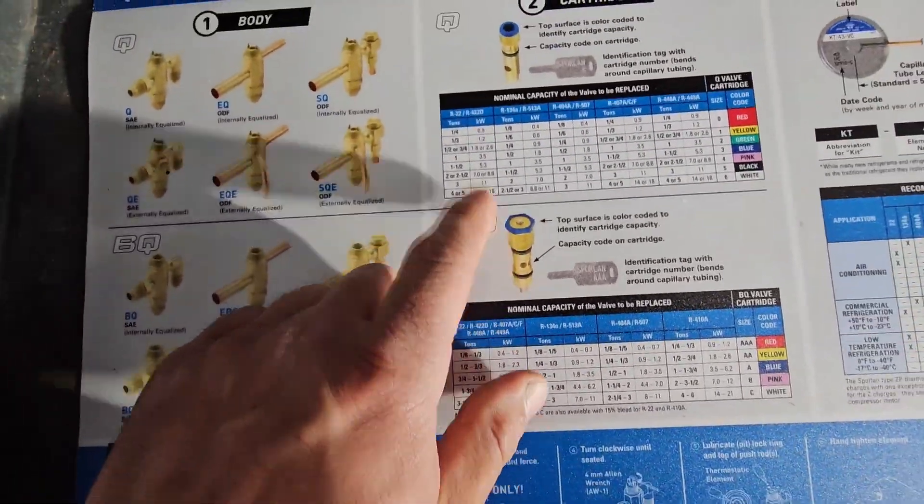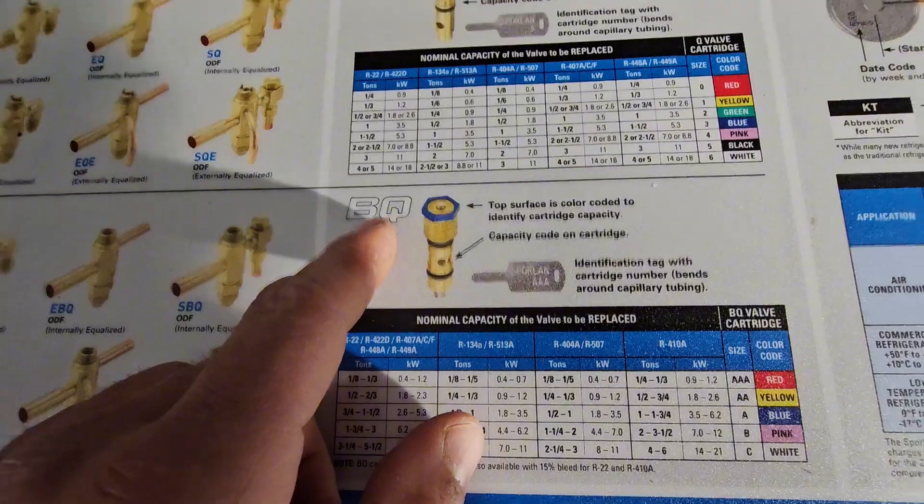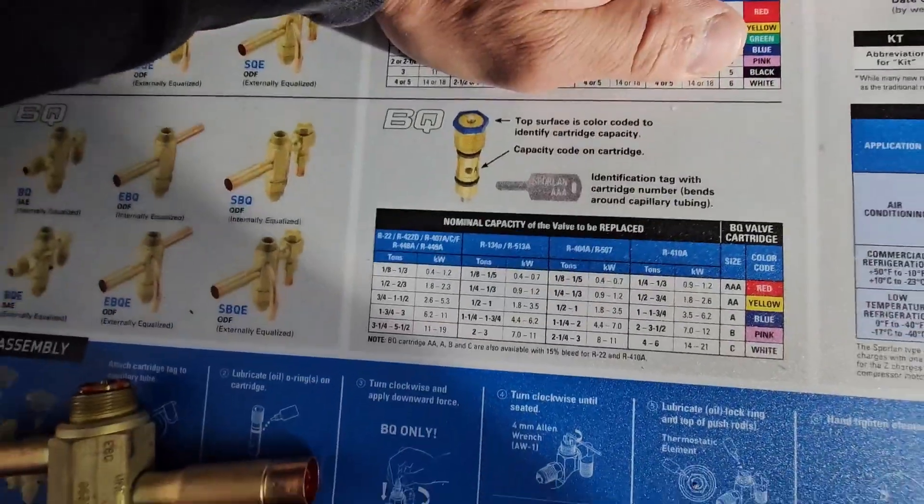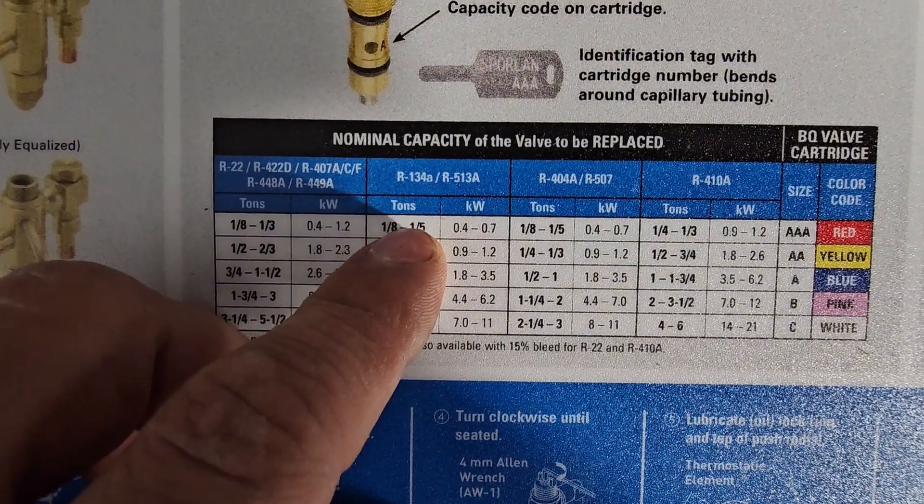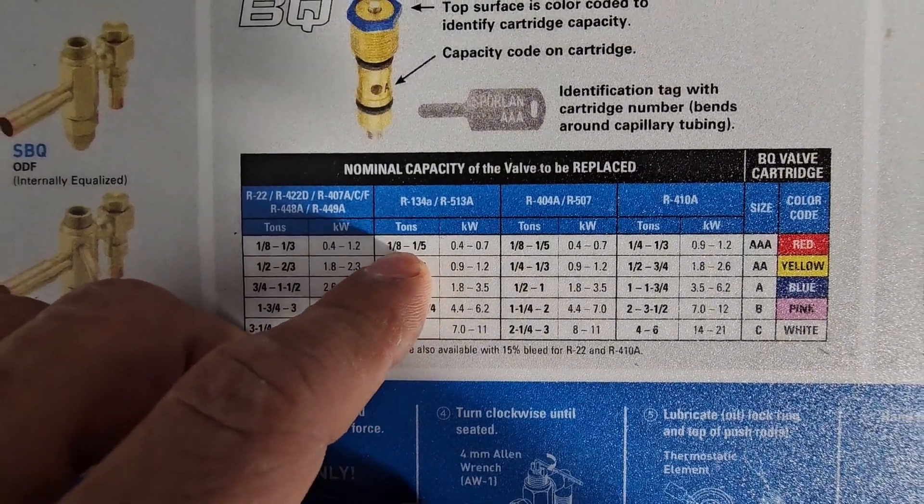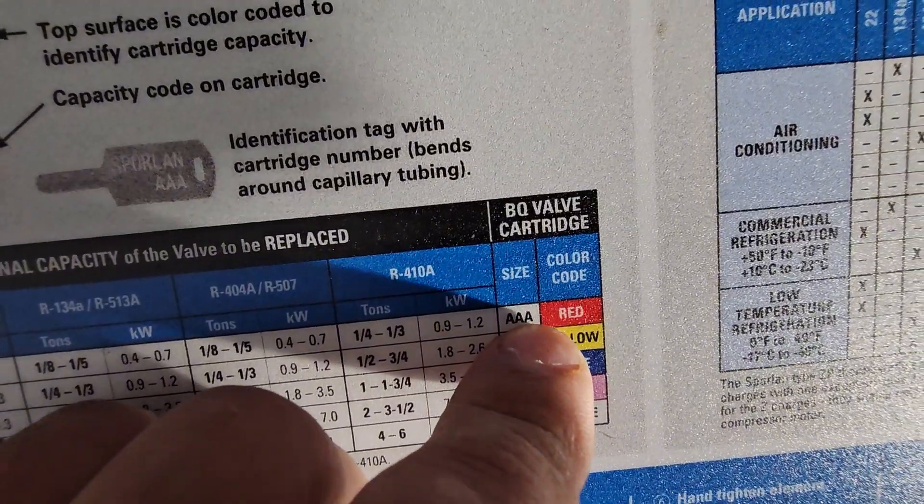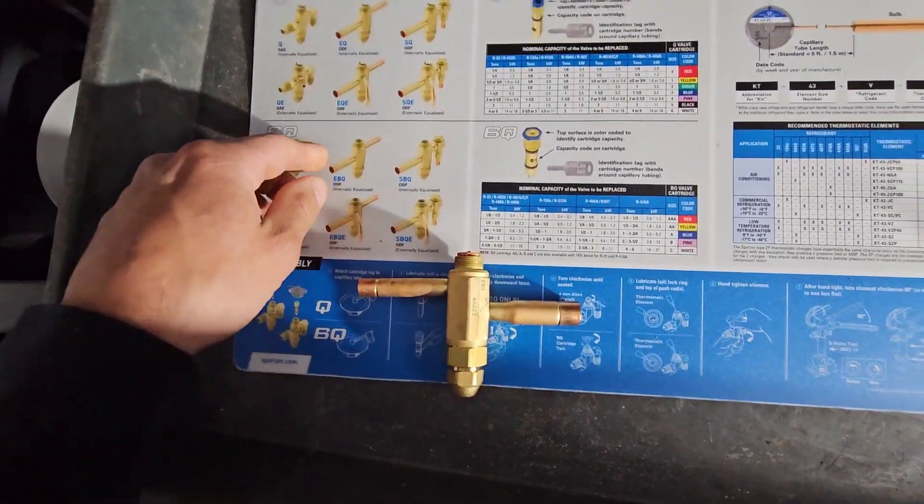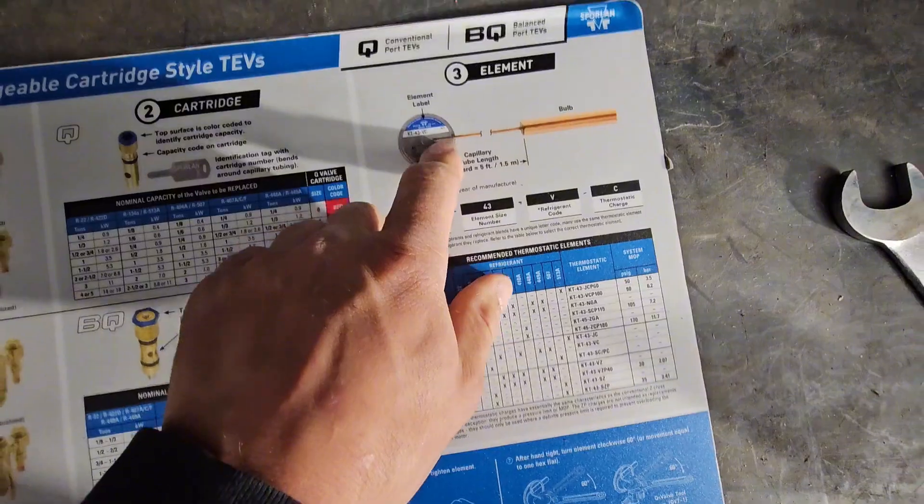I selected an EBQ. Second one is select your cartridge. I'm using a balanced port valve, which I don't want to go into that in this video, but this is for conventional valves. We have a balanced port valve. So basically we're going to be using 134a and we're going to be in the eighth to a fifth ton range, so we want to use a red cartridge, which is triple A, which is what this is. So we've selected our body style, selected our cartridge, now we just need a power element.